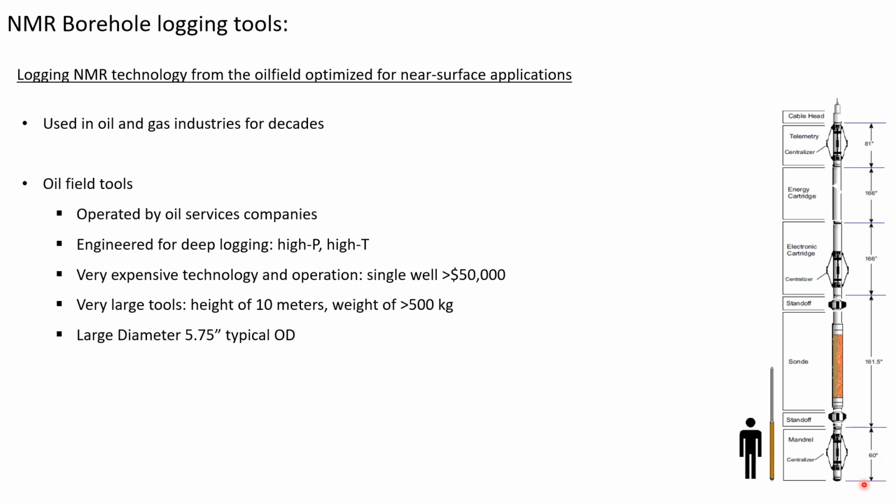So this technology was optimized for near-surface applications relatively recently. And here on the right, you can see the comparison between an oil and gas NMR tool and a near-surface borehole logging NMR tool, which is a big difference between these two.